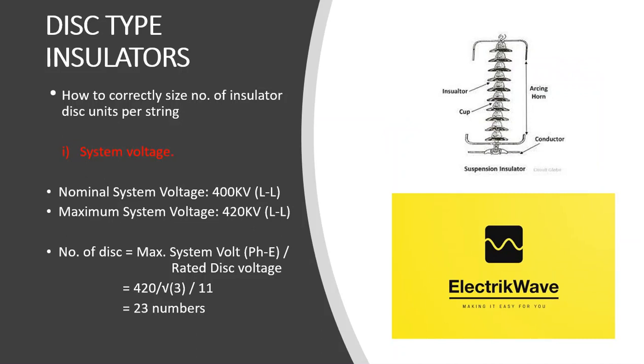Here we will calculate the number of insulator disk units per string based on system voltage. Nominal system voltage is 400 kV line to line. Maximum system voltage is 420 kV line to line. The formula: number of disks per string = maximum system voltage (phase to earth) divided by rated disk voltage. This gives a requirement of 23 disks per string.